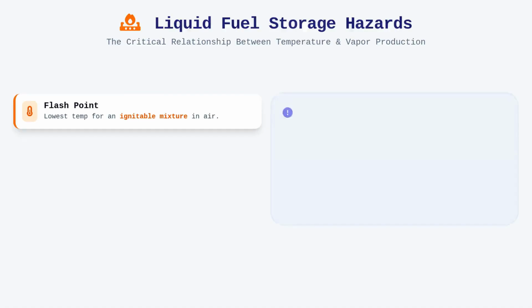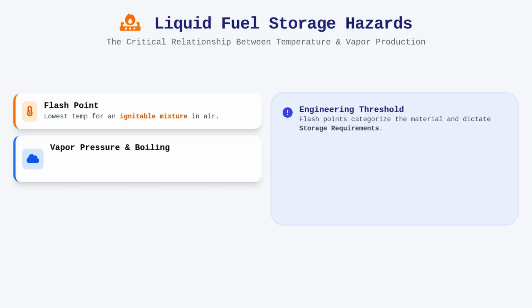Understanding the hazards associated with liquid fuel storage starts with an appreciation for the relationship between temperature and vapor production. Every flammable liquid possesses a distinct flash point, which is the lowest temperature at which it can form an ignitable mixture in air near the surface of the liquid. From an engineering standpoint, this is the fundamental threshold that determines how we categorize a material and, consequently, how we store it. We must also consider the boiling point and vapor pressure, as these variables dictate the rate at which a liquid transitions into gaseous phase, creating a potential blast atmosphere.